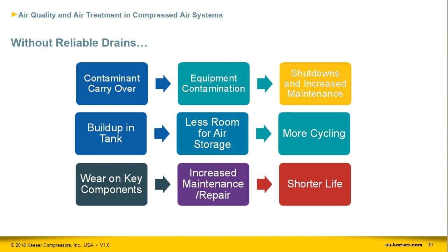With tanks, there are other negative impacts. Moisture can build up quickly in the tank, particularly during summer months. The more water, the less room for storage. The less storage, the more your compressor will cycle on and off. As we said earlier, this increases wear and stress on valves, motor starters, air ends, and coolers. The results? More frequent maintenance, more frequent repair, and greater downtime. There's also shorter machine life to worry about and an elevated energy cost.